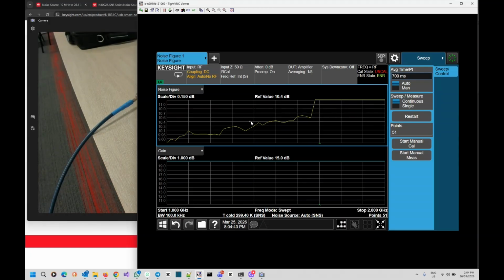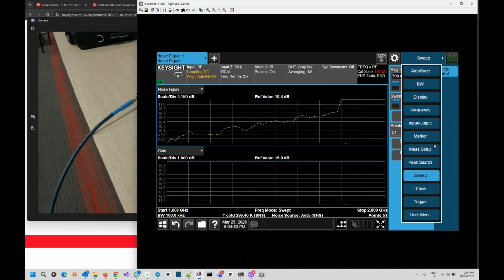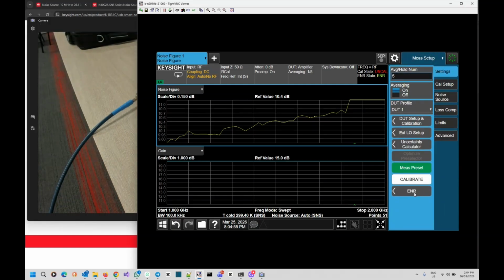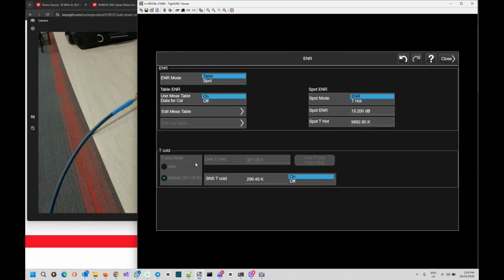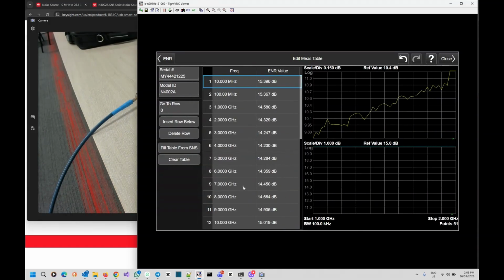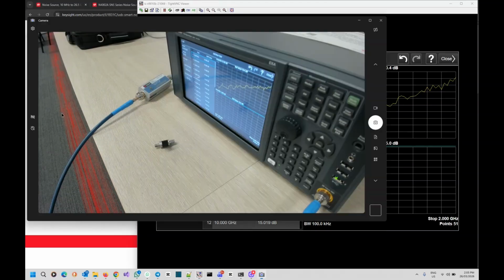Once we're happy with the setup, the start-stop frequency, the resolution bandwidth, the number of points, and we make sure that the noise source is shown here, the next thing we want to check is to make sure the ENR table is loaded. So we go to measure setup, go to ENR, and from here, edit measure table. You should get all the information correctly from the noise source here.